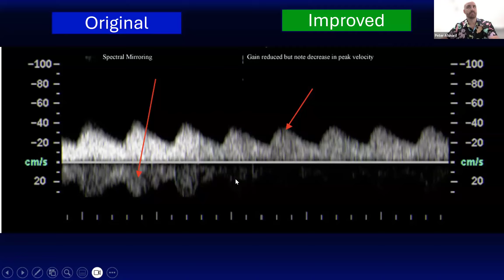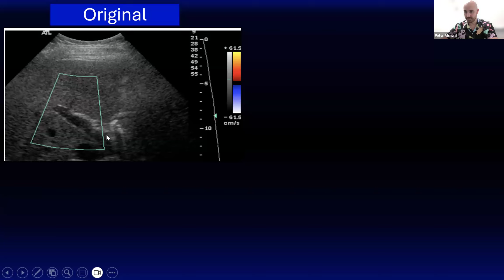Okay. Here we're measuring some flow through the portal vein. And so nothing. Portal vein thrombosis, call surgery or heparinize. So to address this, we can adjust the sensitivity of the Doppler flow. Okay. And this is not an adjustment to gain. This is actually an adjustment of how the machine's shooting flow out. And so you see here, by adjusting the scale and adjusting this thing called the wall filter, you're able to pick up this lower flow state.